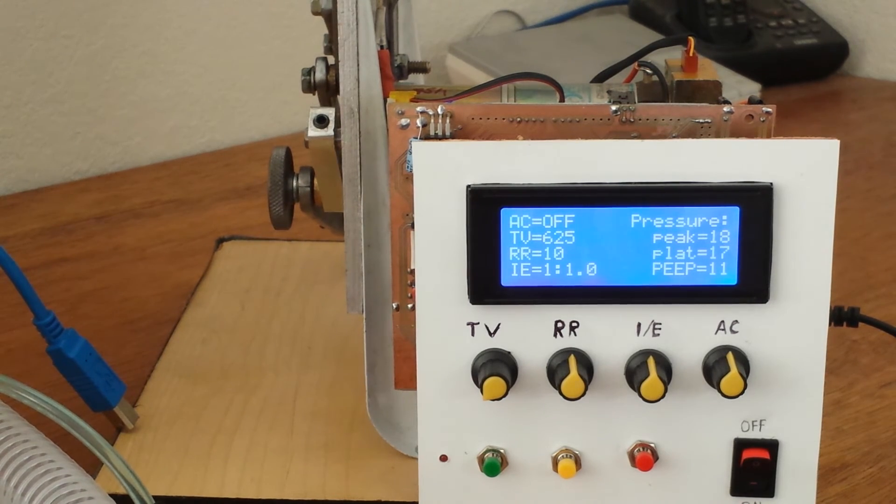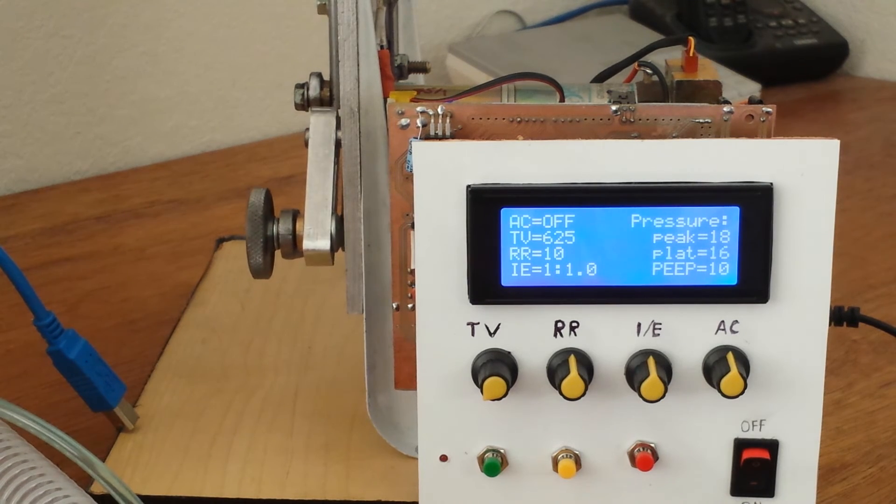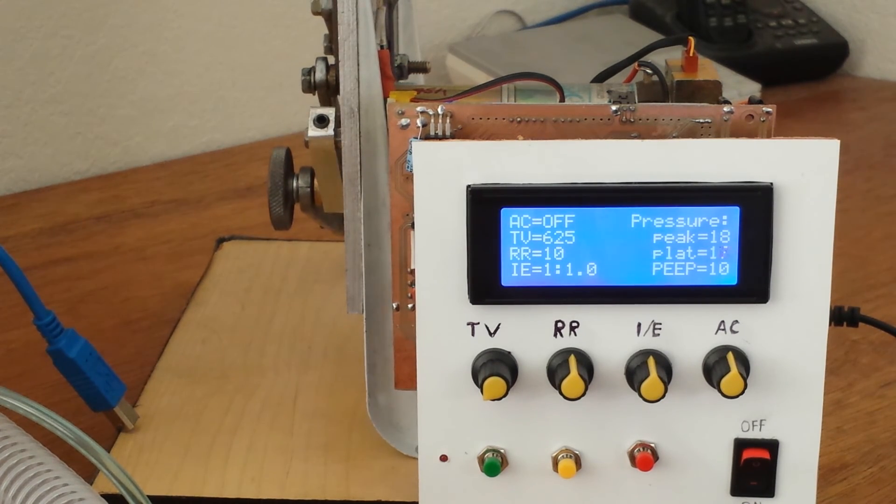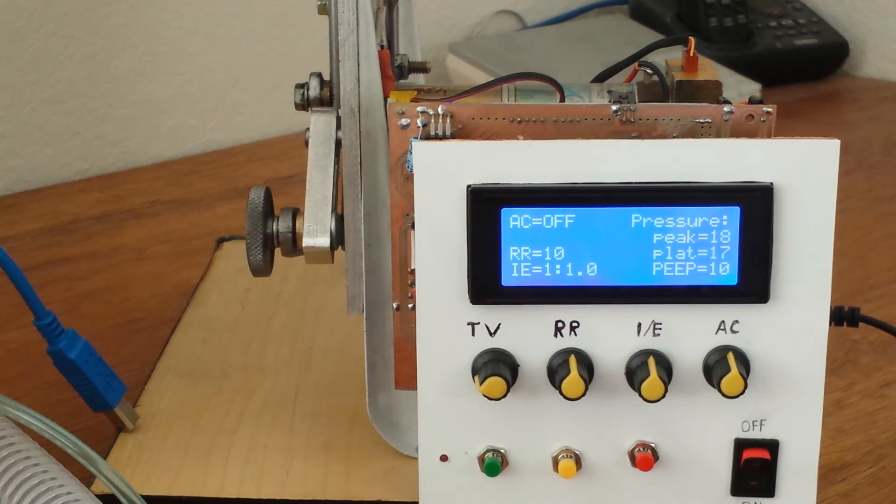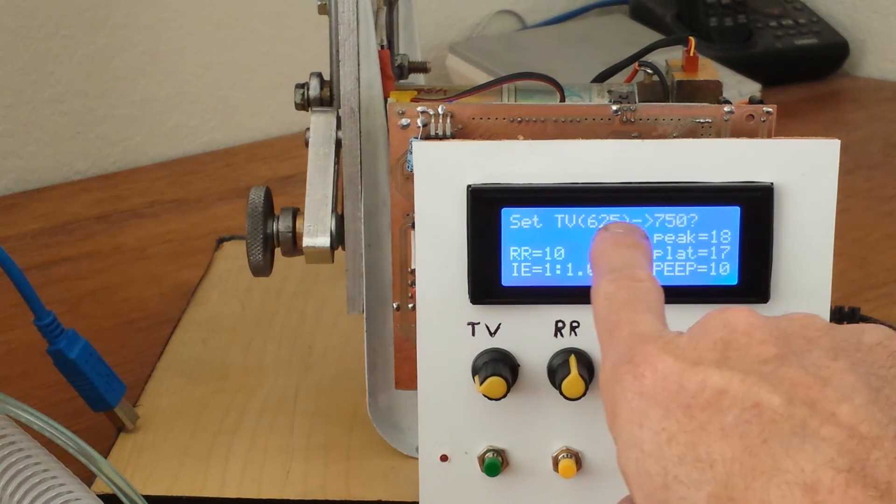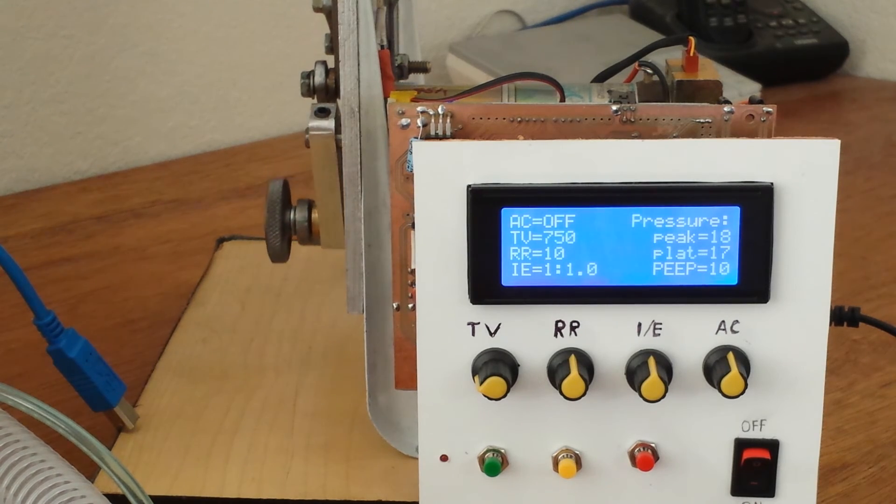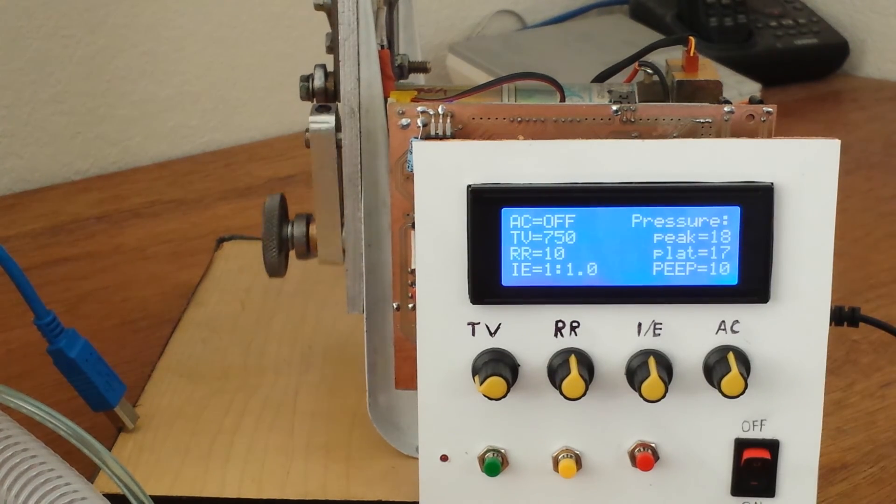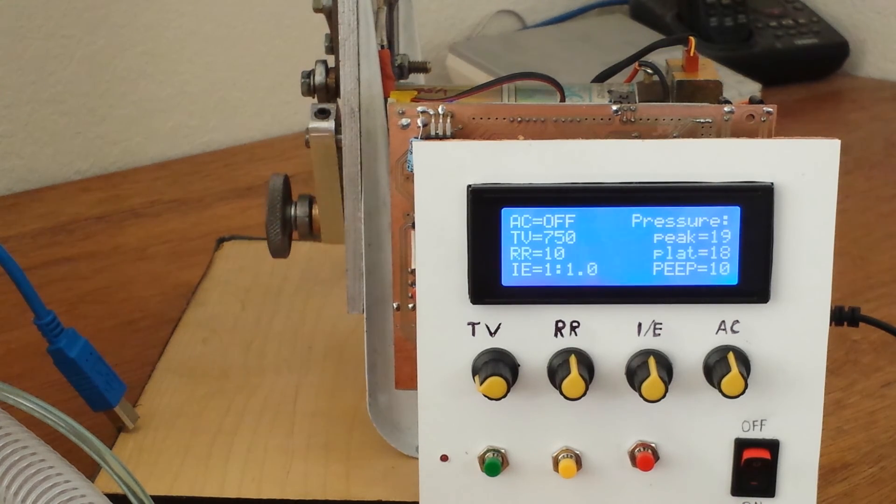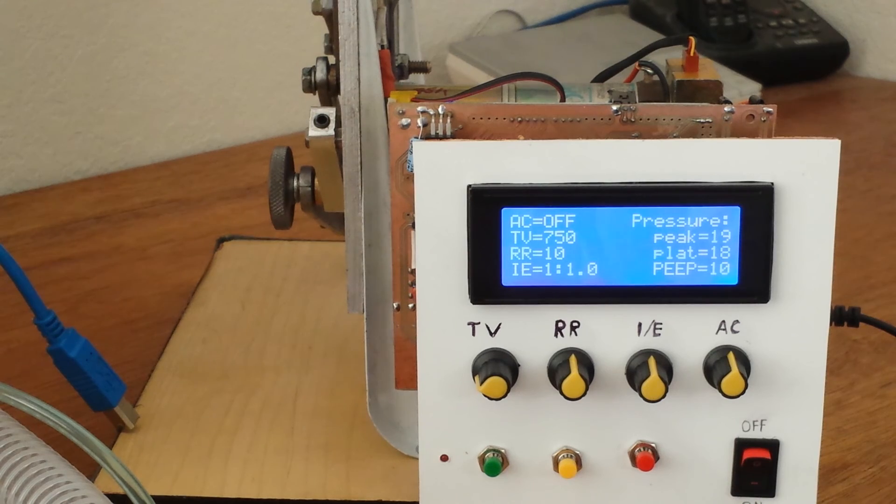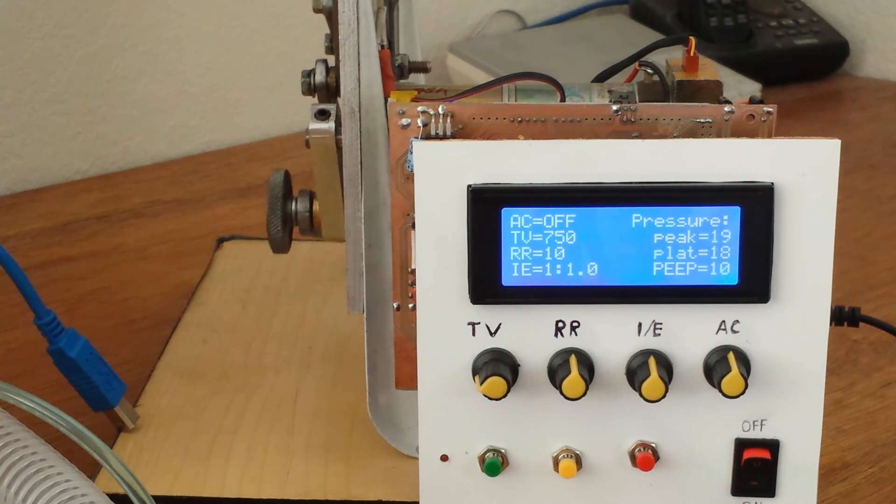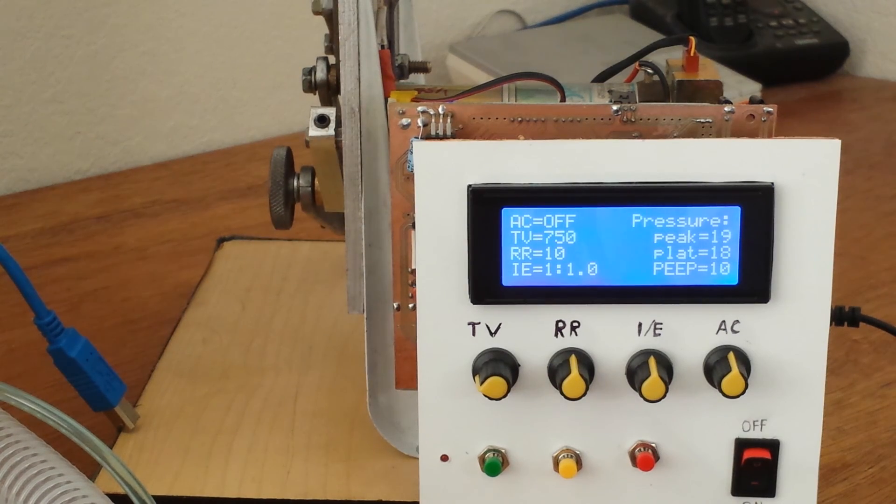And PEEP, if I wanted to tweak it down, I will manually have to adjust the peep valve. So I just turned it down to 10. If I would set the tidal volume and not do anything, it will blink for a while and then an alarm comes on asking do you want to change it, do you want to really set it. If you do, you just hit set. There you go. So breathing assist is working now since we have a pressure sensor. I've been running it for days now, it doesn't seem to be a problem with it. I'll keep you guys posted. Thanks for watching.